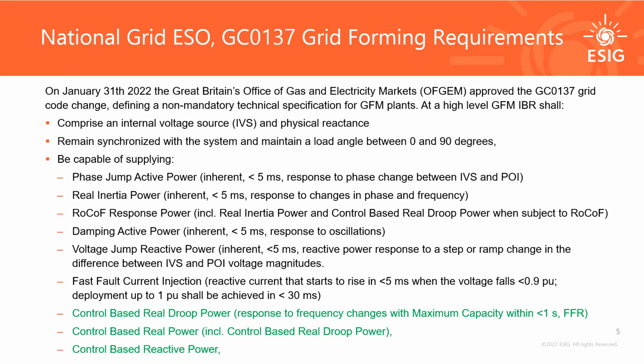Currently it's already being procured through a number of tenders where National Grid asks for certain amounts of short circuit strength or inertia—short circuit strength in a local area, or inertia system-wide—and inverter-based resources offering into this tender have to comply with these new requirements in the last tender phase, the one ongoing right now. The previous stage just concluded, and 5 grid forming batteries were already procured and awarded as part of this tender. So this is already happening.